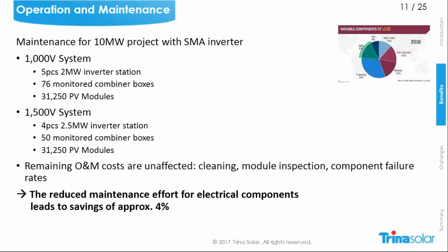If we now take a look at operation and maintenance, it's basically, for example, checking the components, which you have to do frequently, one time per year or every 6 months. In the example here I have used a 10 megawatt plant. For the 1000 volt system we have 2 megawatt inverter stations. For the 1500 volt system it's one inverter station less, because the size is 2.5 megawatt instead of 2. But the bigger impact is on the monitored combiner boxes. In the 1000 volt system you have 76, and in the 1500 volt system you have 50. As you can see, the number of modules is still the same. If you calculate the benefit in terms of operation and maintenance cost, you have approximately a 4% benefit.